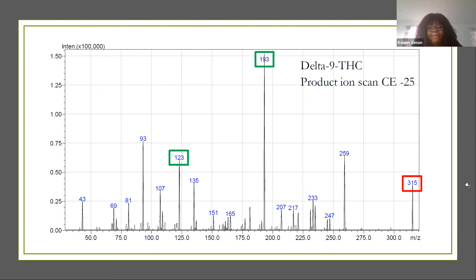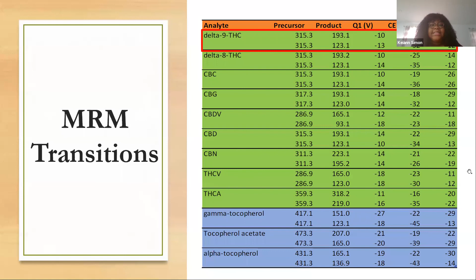This is a summary of the mass spec optimization of the standards we have tried so far by using LC-MS-MS. There are 9 cannabinoid derivatives represented in green and 3 vitamin E derivatives represented in blue. From the ion scan, using the example of delta-9-THC, we see, as previously mentioned, the parent ion or precursor ion at 315 and the most intense ions at 193 and 123. This gives us 2 ion transitions for delta-9-THC. Next slide, please.